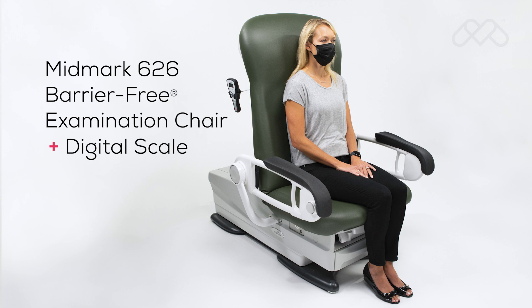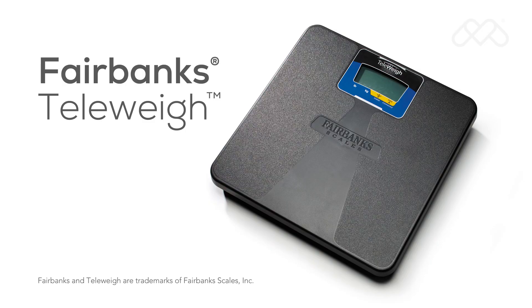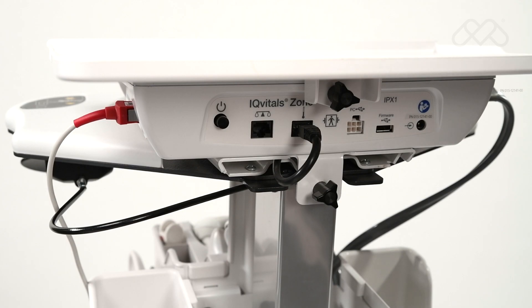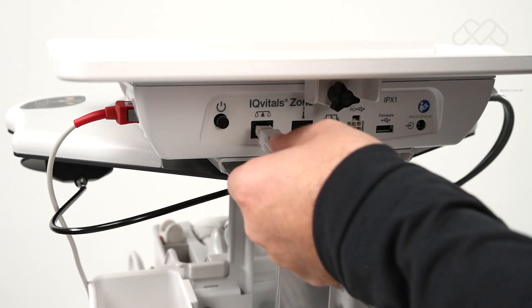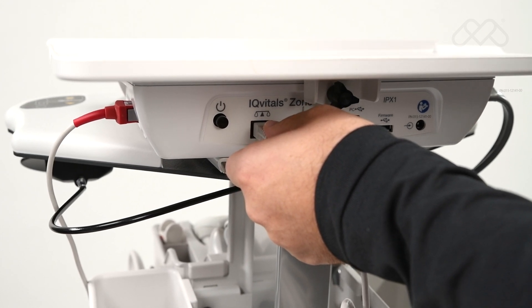Weight capture: The IQvitals Zone device is compatible with serial connection medical-grade approved digital scales, such as the Midmark 626 barrier-free examination chair with integrated digital scale or the Fairbanks Teleweigh digital scale. When a compatible scale is connected to the device through the RS-232 port on the back of the device, IQvitals Zone will automatically detect that the scale has been connected and is ready for use.